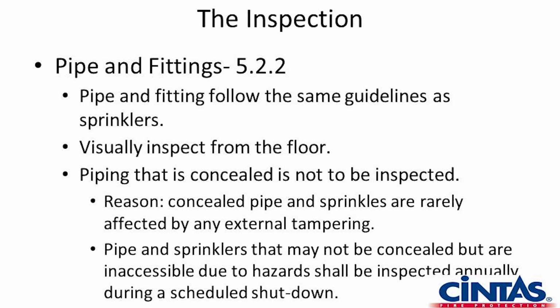It goes on in a different section of NFPA 25 to talk about when there are accessible areas to concealed piping and sprinkler heads, that during shutdowns or other instances like that, that's an opportunity that we can take to look in those concealed spaces, as long as we don't have to damage the structure to get to what we're trying to see. Reason for that is the concealed pipe and sprinklers are rarely affected by external tampering. I mean, nobody has spray paint, nobody's painted a ceiling and covered the sprinkler head over with paint. Here, there's the section. Pipe and sprinklers that may not be concealed but are inaccessible due to hazards that are inspected annually would be inspected during a shutdown.